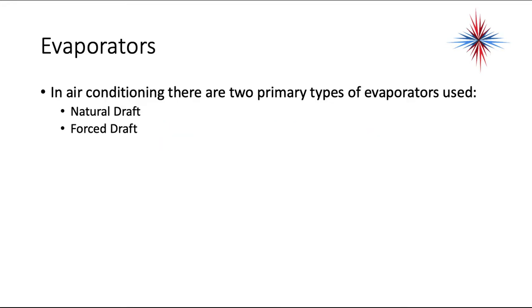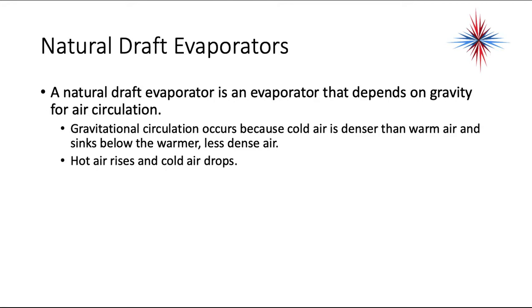There are two primary types of evaporators used in air conditioning: natural draft and force draft. Natural draft, as you'll see in the next picture, you see a lot of times in big warehouses. They're not often used in conditioned space other than big cold storage warehouses, and they could almost be considered refrigeration. Natural draft evaporators depend on gravity for air circulation. Gravitational circulation occurs because cold air is denser than warm air and sinks below the warmer, less dense air — hot air rises and cold air drops.